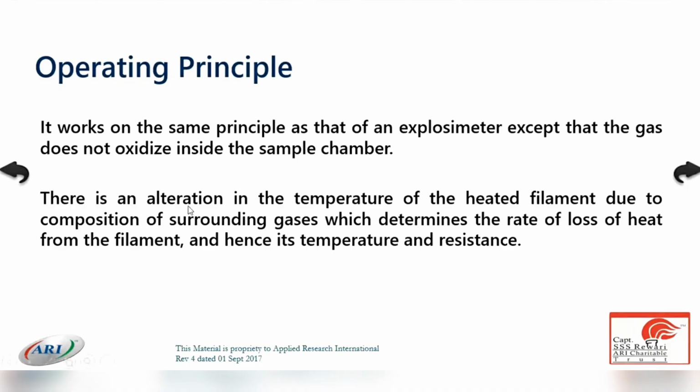There is an alteration of temperature of the heated filament due to the composition of the surrounding gas. The sample gas comes in contact with the heated filament and absorbs the heat from the filament, and as a result, the temperature of the filament is reduced. The rate of loss of heat from the filament affects its temperature and resistance.